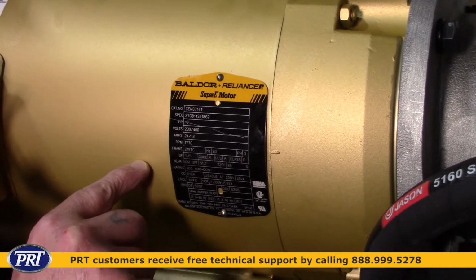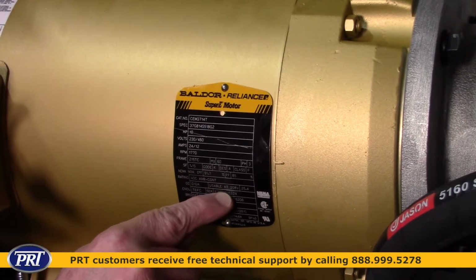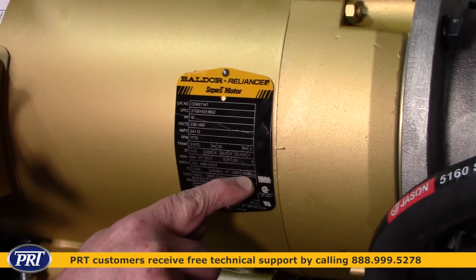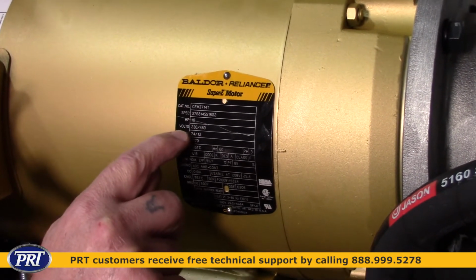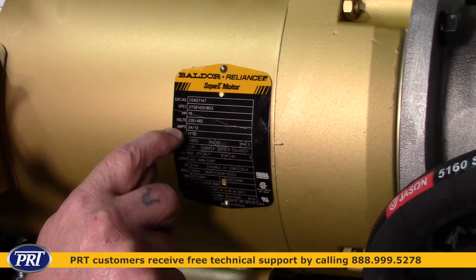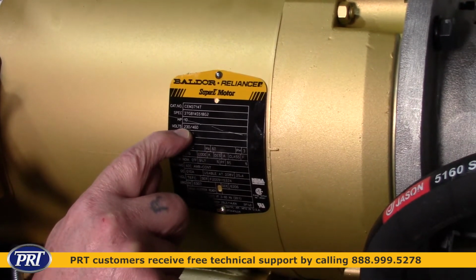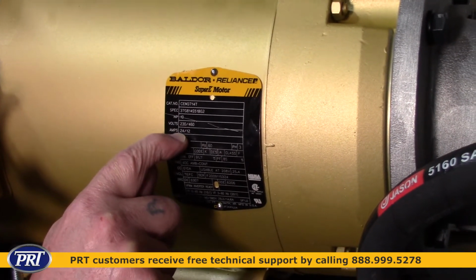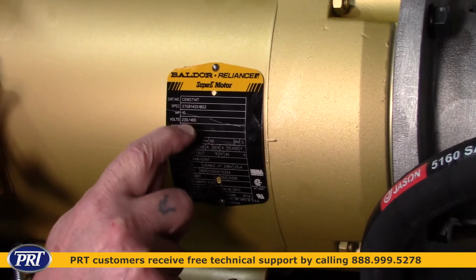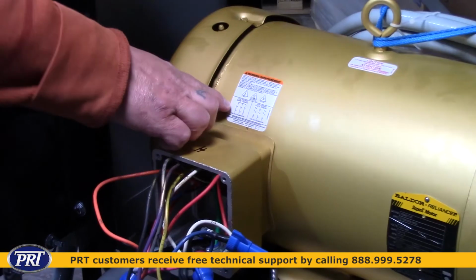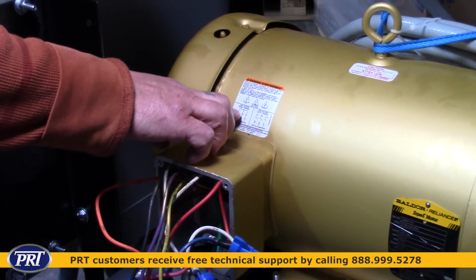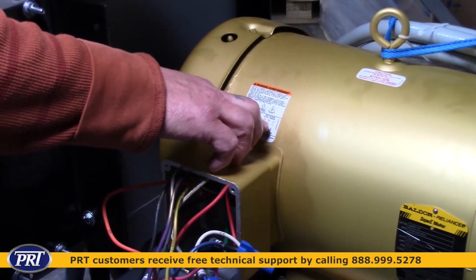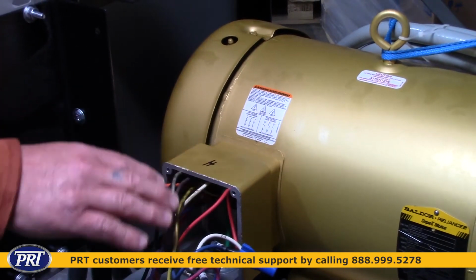This is also usable at 208, but they put it down here where it says usable at 208 at 25 amps. So what you're going to follow when you adjust your amperage per your voltage is, if you're going for 230 volts, your amperage would be 24 amps. If you're at 460 volts, your amperage would be 12 amps. This tag here is showing you how to wire your low voltage or your high voltage on the motor.